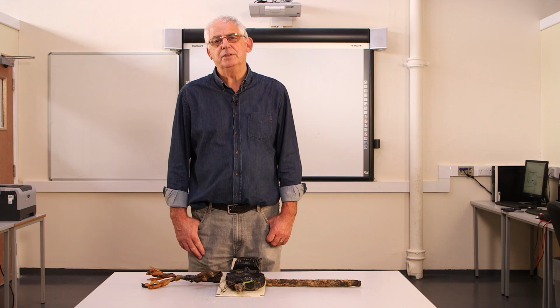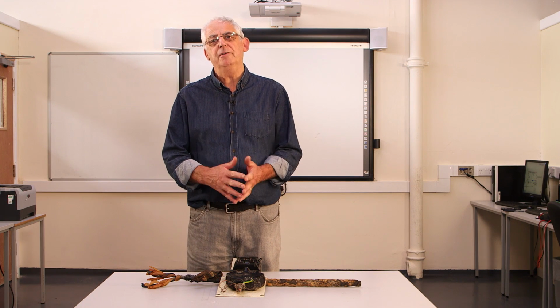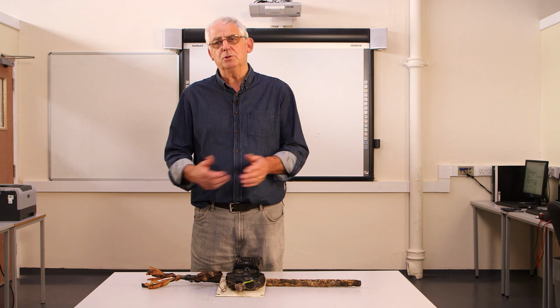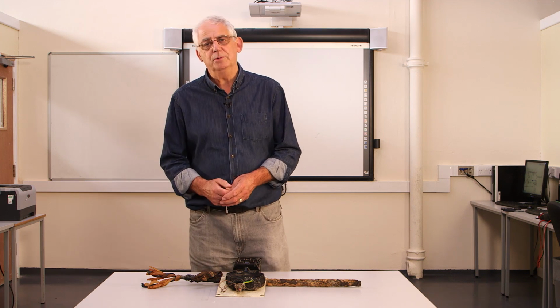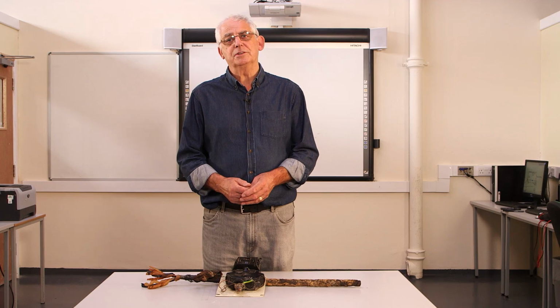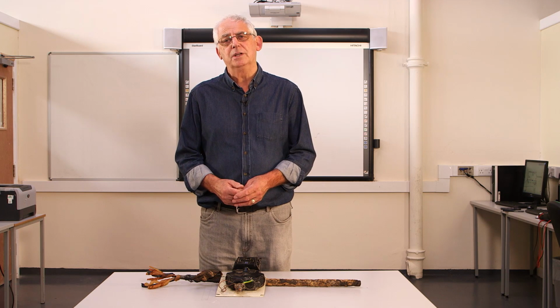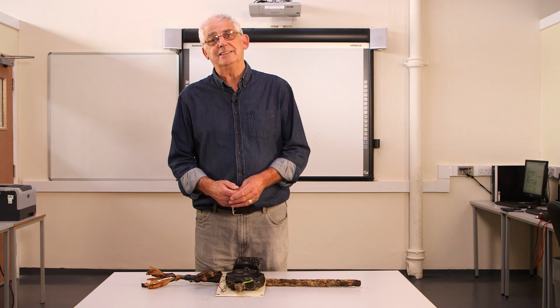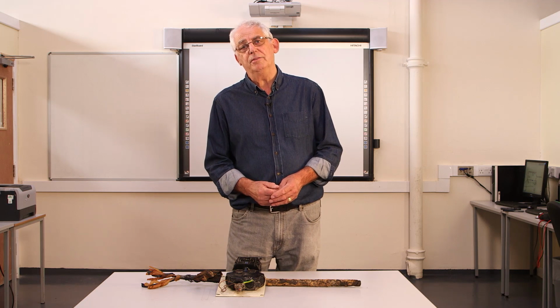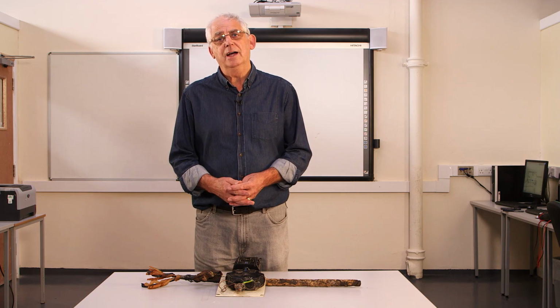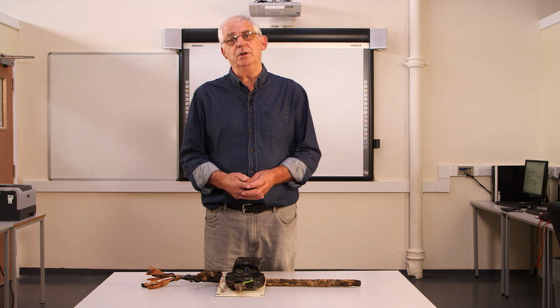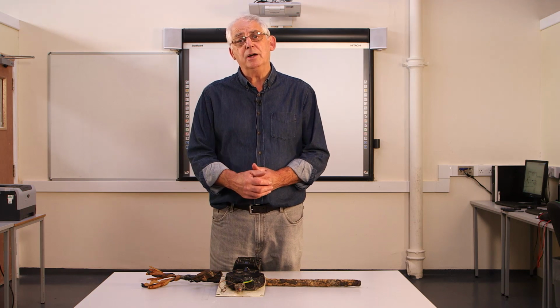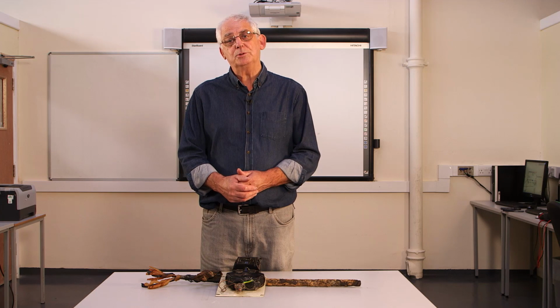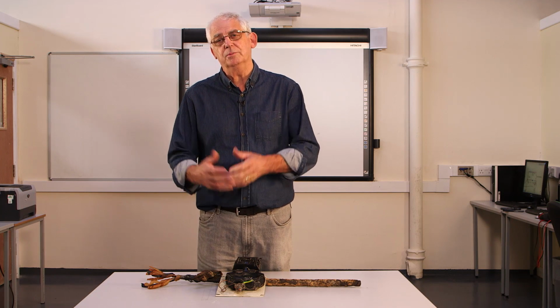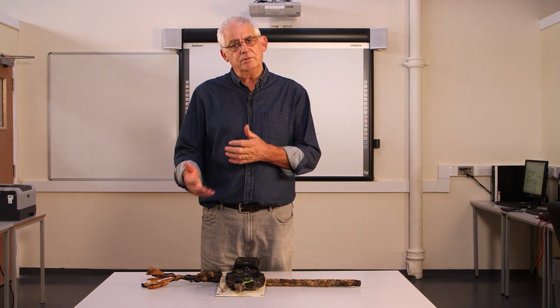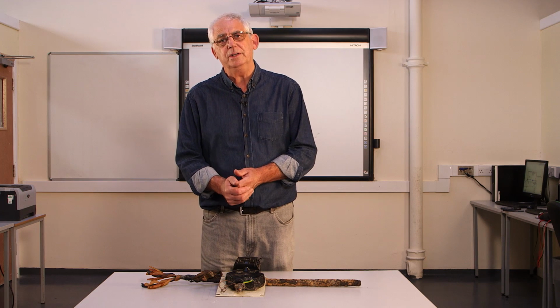Just want to describe the different types of earthing arrangements we have in properties. We'll just talk about single phase for the moment. We have three different types in general use. The first one is a TT system, which we have an overhead supply, and normally we would supply an earth rod at our house or building, which would give us our earth, if you like, and we need to fit an RCD. Obviously, they're still used quite commonly.